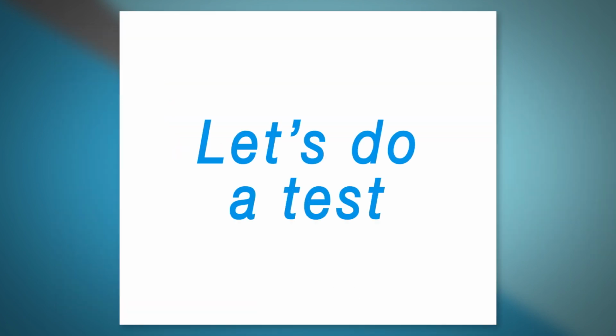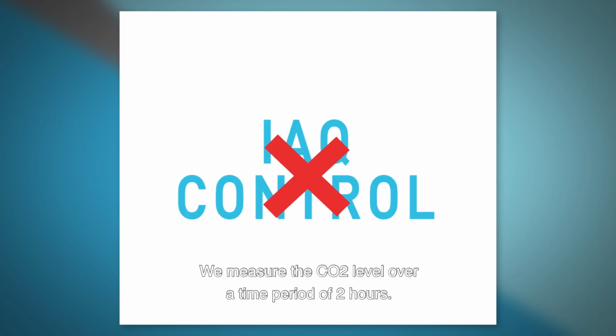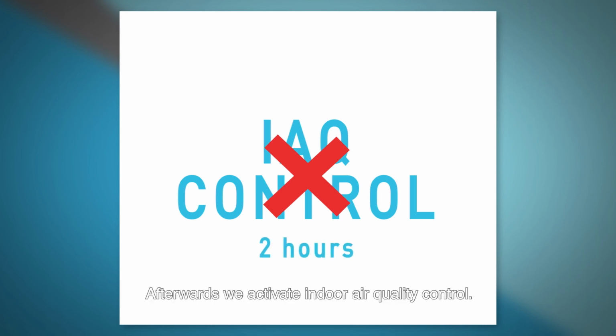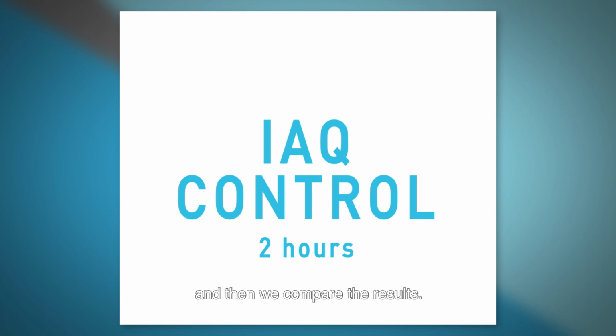Let's do a test. First, we start without indoor air quality control. We measure the CO2 level over a time period of 2 hours. Afterwards, we activate indoor air quality control. We measure again the CO2 level over a time period of 2 hours and then we compare the results.